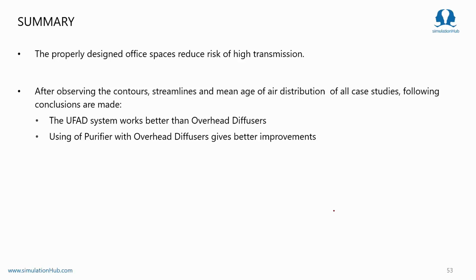If you have already installed an overhead diffuser system, it is always advisable to go with a purifier to control the airborne infection. In this way, we can design effective ventilation systems in office spaces, and we can reduce the high risk of transmission in office space. Again, I want to point out that these results are limited to the inputs we have considered.